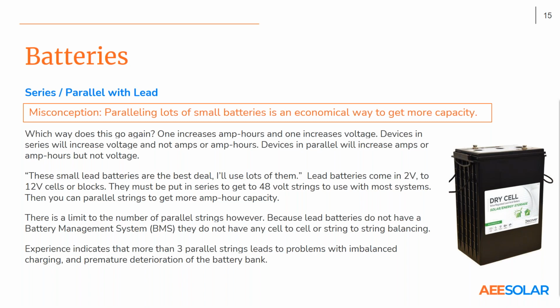And you put them in series, you get 48 volts, you got 4 in series, but then people put lots and lots of parallel strings together to get their capacity up to what they want. And with the lead batteries, it just doesn't work very well. And this has just come from experience over the years. Even before solar was around, this was still known, back from the early 1900s, actually, where if you put too many parallel strings, the cells get imbalanced to each other. And the more imbalance there is, the more some get overcharged and the more some get undercharged, and they're both damaged and have premature failure.